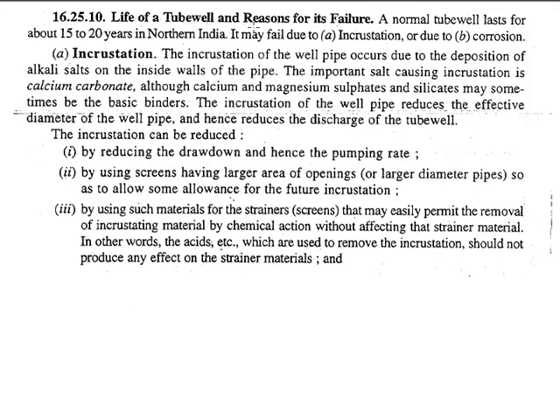Apart from all of these, there is a certain lifespan for such tubewells and certain reasons for their failure. They are considered to have a lifespan of about 15 to 20 years in northern India. Such tubewells fail due to two main reasons: the first is incrustation, and the second is the corrosion process.